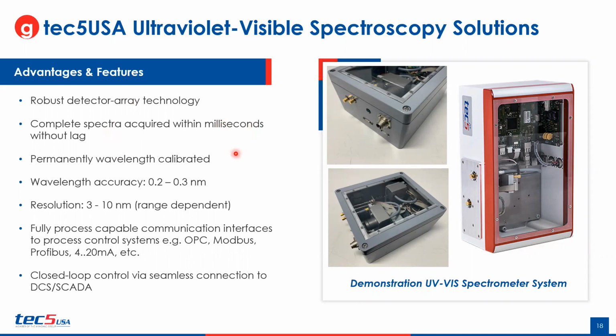These devices are also permanently wavelength calibrated. So once an instrument is installed in the location, it is permanently wavelength calibrated, and no shift in the wavelength is anticipated, and ultimately it is a set and forget device when it comes to the wavelength calibration. The accuracy of this device is on the order of 0.2 to 0.3 nanometers when it comes to your wavelength accuracy, with a resolution of 3 to 10 nanometers.